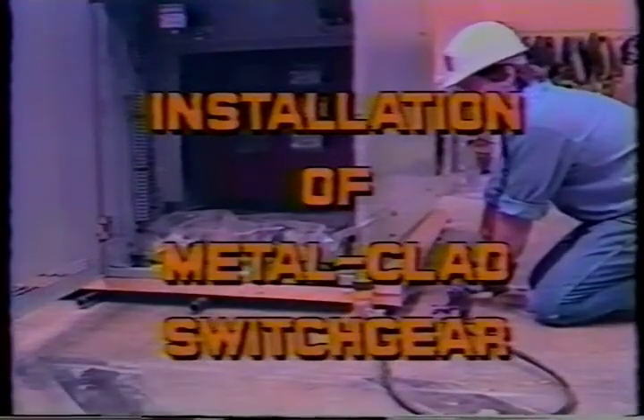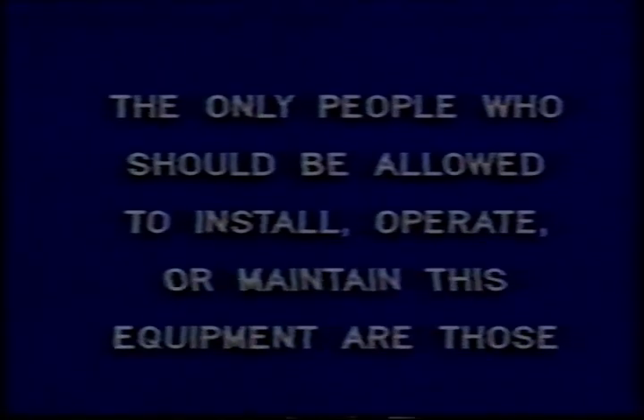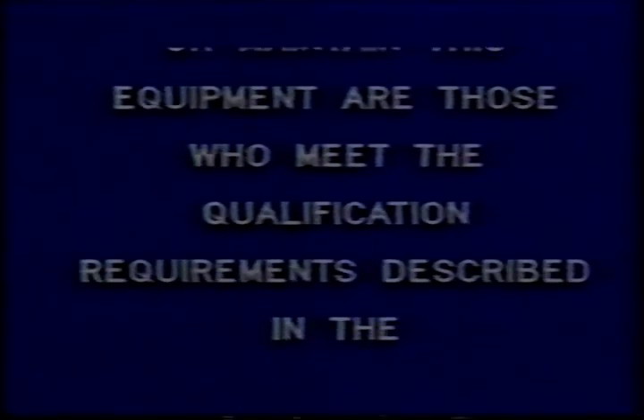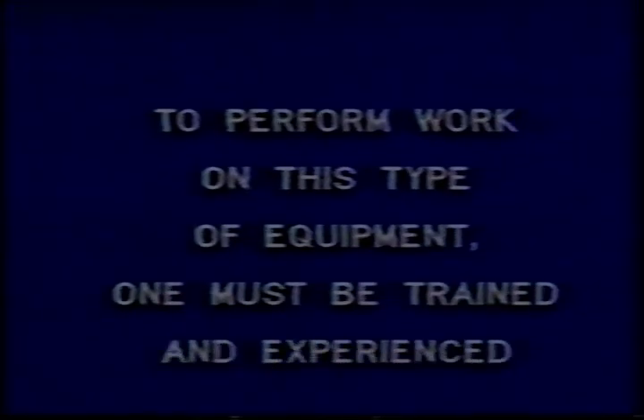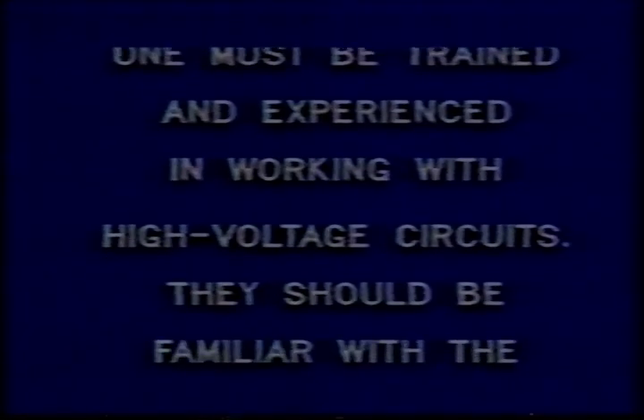Before proceeding with the installation of this equipment, it is important that you are familiar with and clearly understand the following recommended safety practices. Before attempting to do any maintenance, always be sure to de-energize both the primary and secondary circuits. Never leave a breaker in an intermediate position in its compartment. Always crank the breaker into the fully connected or withdrawn position.